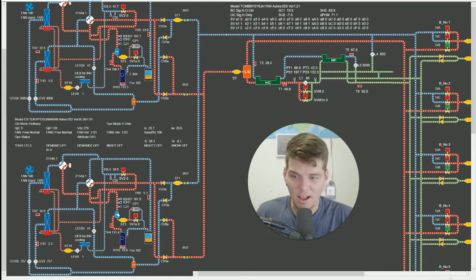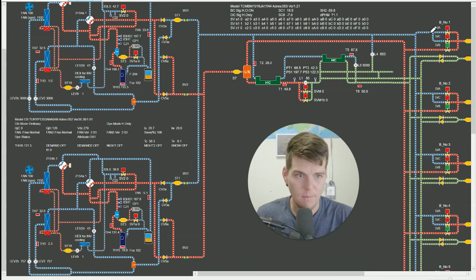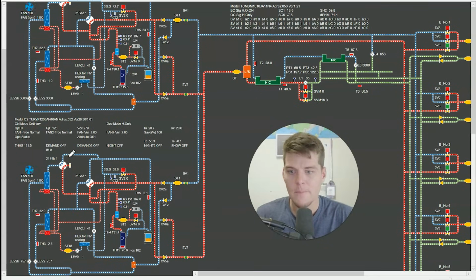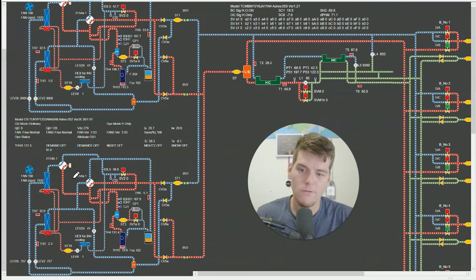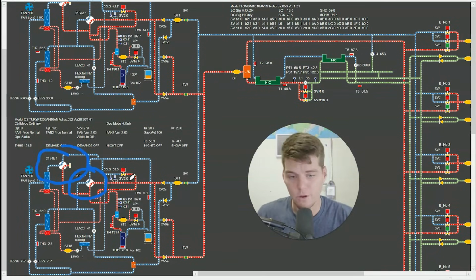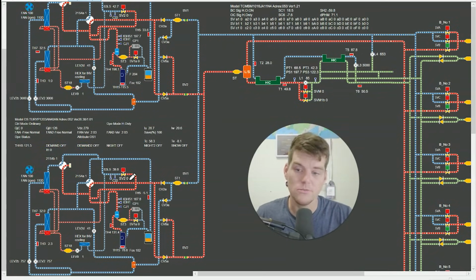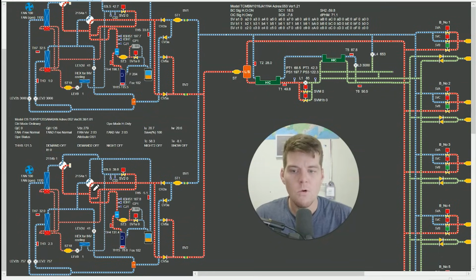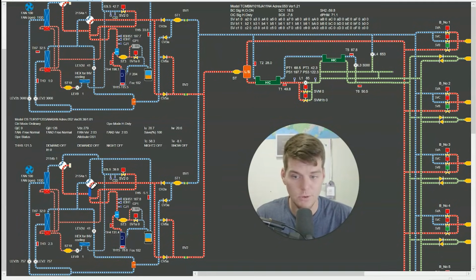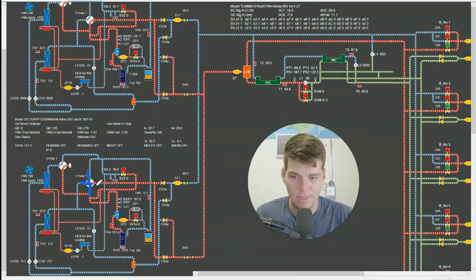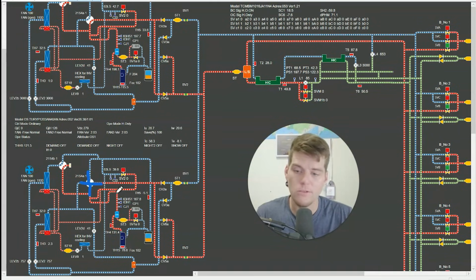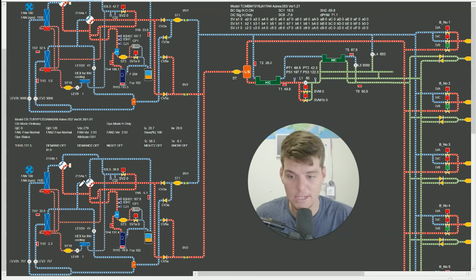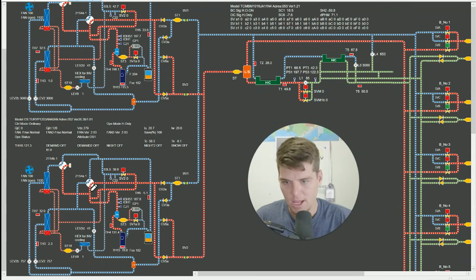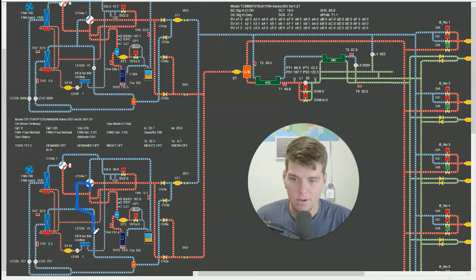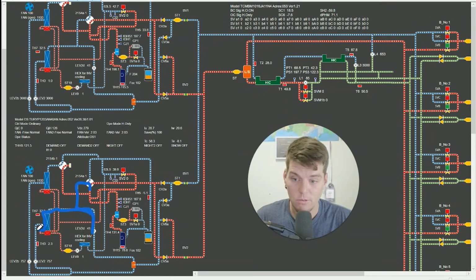Well, that is because of a common issue with this equipment, come to find out. Four-way valves. Well, think about four-way valves, and they're designed to do what? They're designed to shift the flow of refrigerant to one side or the other, right? To redirect flow of refrigerant in a system. Well, what happens when these four-way valves fail? Well, for this one here, if this is actually turning left, and that connects over here to the right, then we would follow that flow of refrigerant and say, okay, well, if I was dumping hot gas here, what would that look like? Well, it would go from here, try to go that way, maybe it can't go that way, those pulses are low, it would go through here, and it would show up what? It would show up here on this sensor.